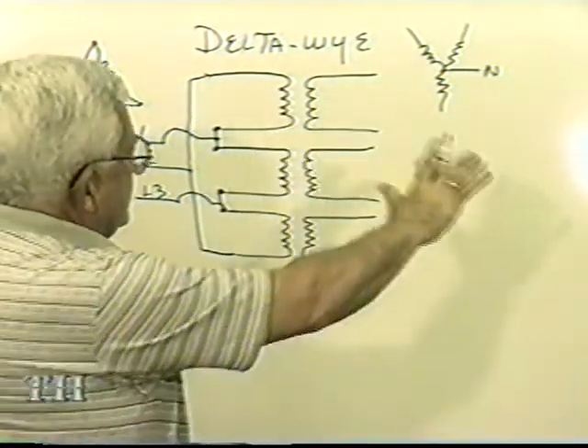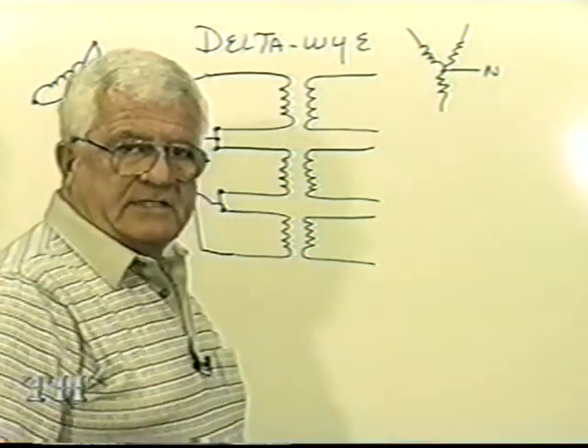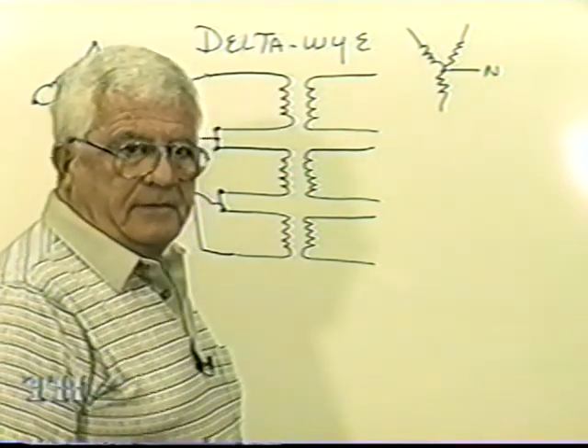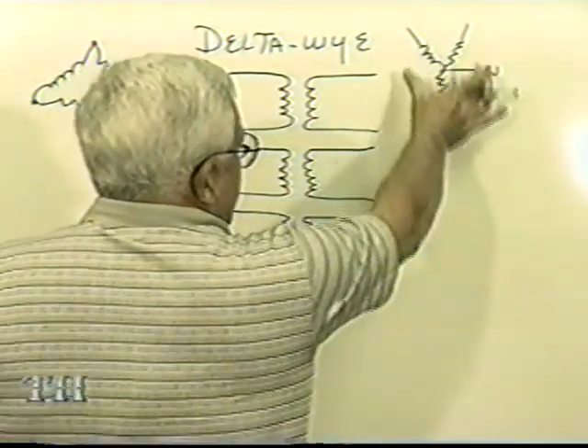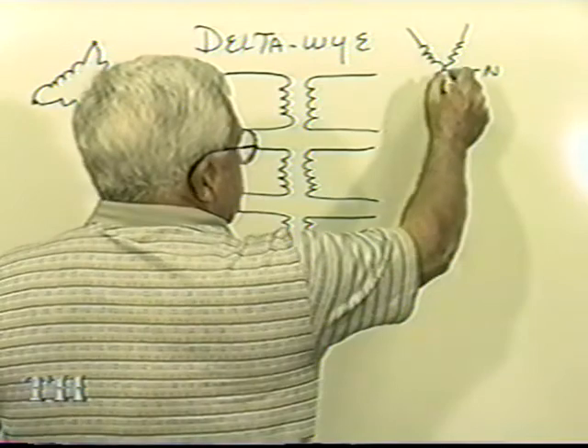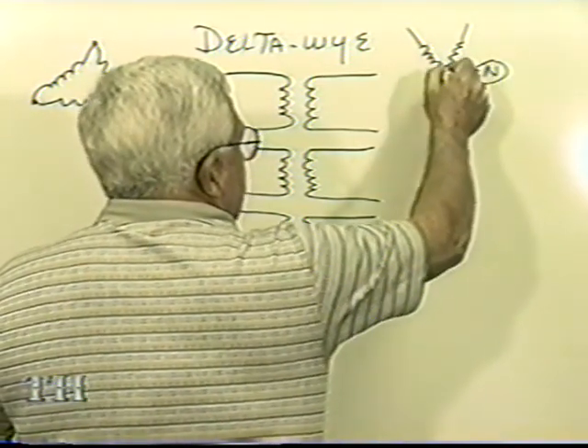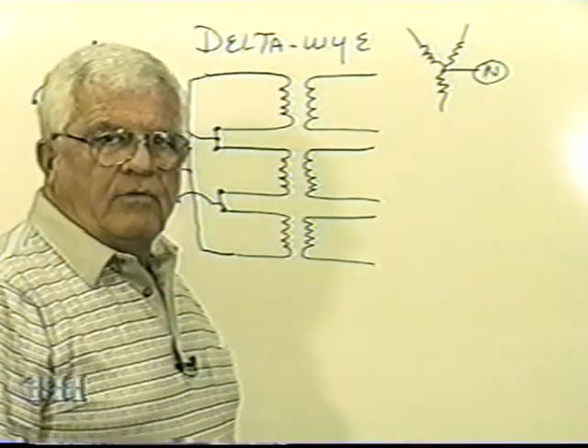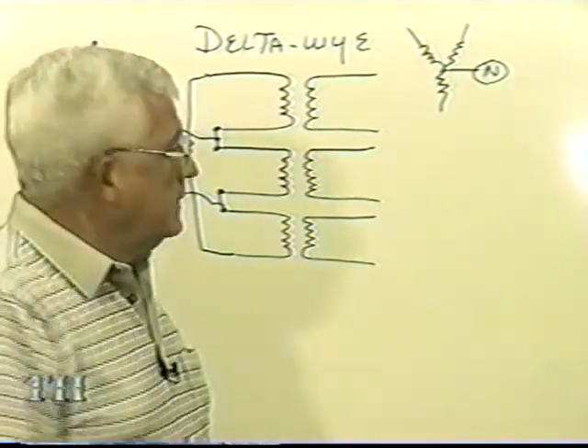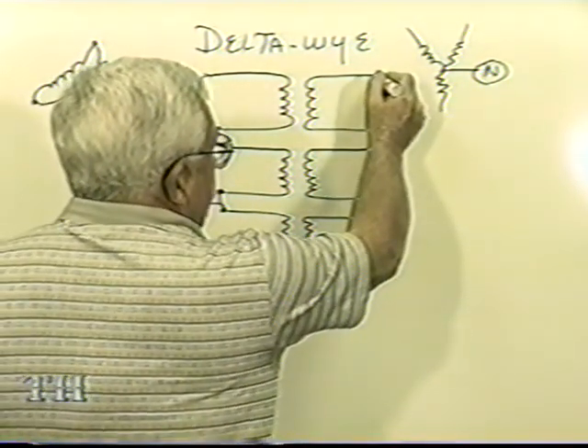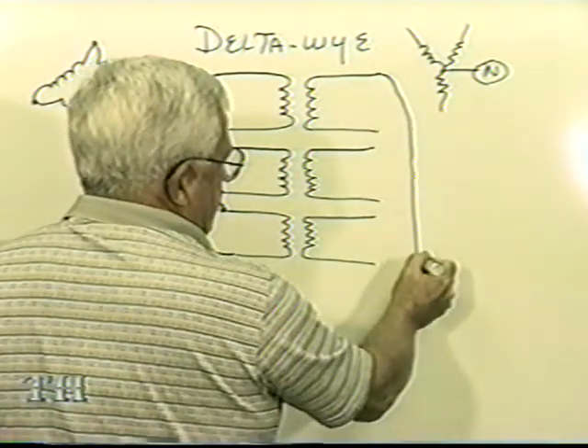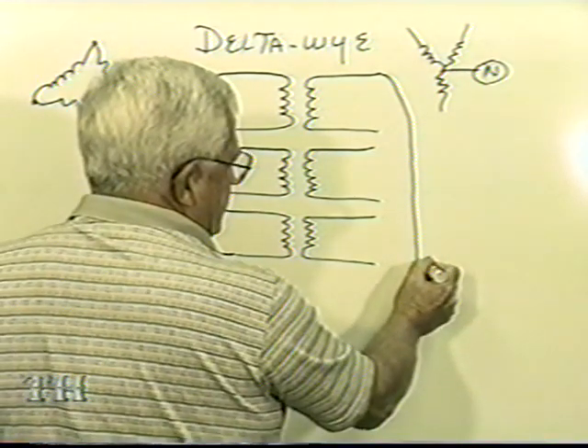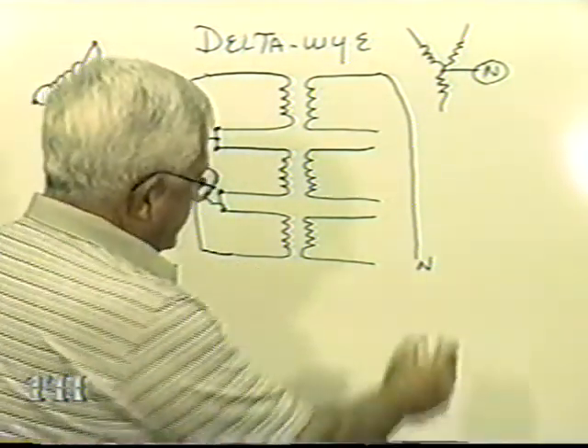Now if I come over here on the secondary, that's going to be my lower voltage on a step down. See how this looks like a Y? It shows the neutral being connected to all three coils. I'm going to start right here at the top, bring this wire down, and call it my neutral. This will be my neutral.